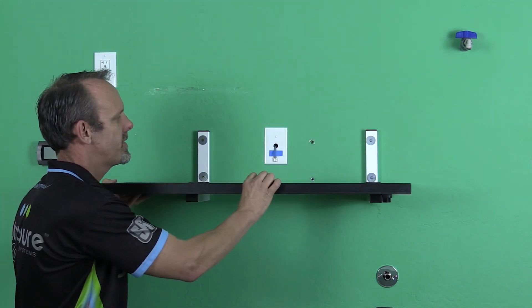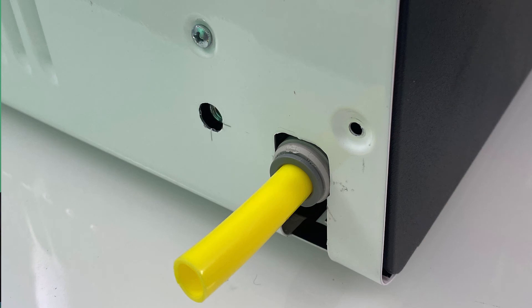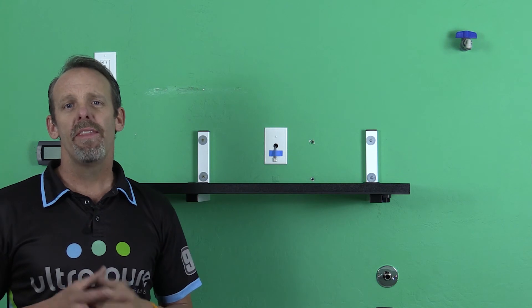At that point, you can put the pan on and it's ready to go. If you put the humidifier on its back very gently, you'll find there is a push connection fitting in the corner. In the clear bag, there'll be a yellow tube. It's about three quarters of an inch long. You're going to want to push that yellow tube into the JG fitting. And that's going to be your primary drain. So when you get the humidifier lifted up onto the tray, that tube is going to go directly into the bulkhead fitting. It's going to align perfectly in the center. So if any water drains out of the humidifier, it's going to drain right into the bulkhead fitting. So you don't get any water in the tray.